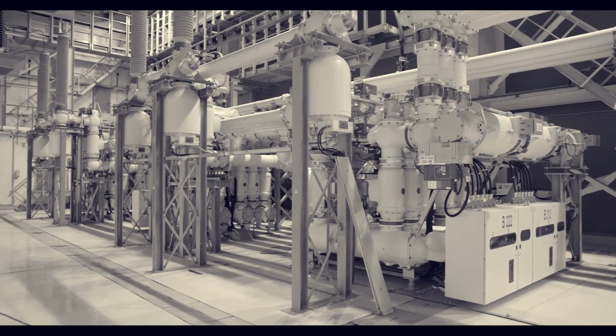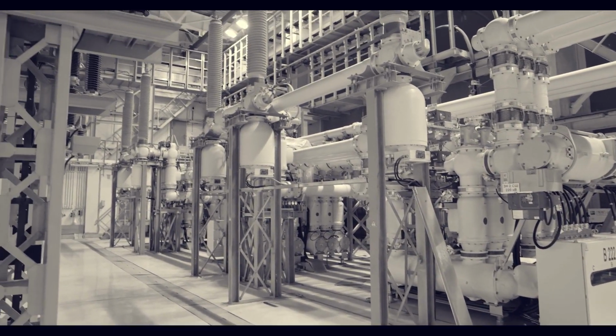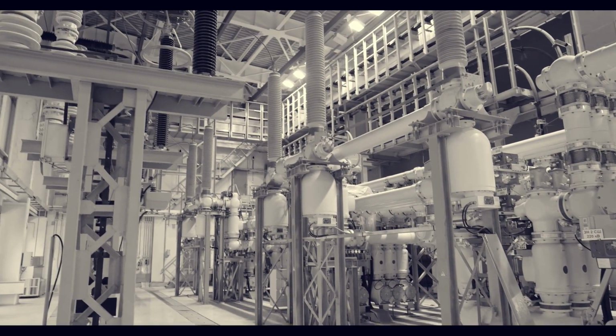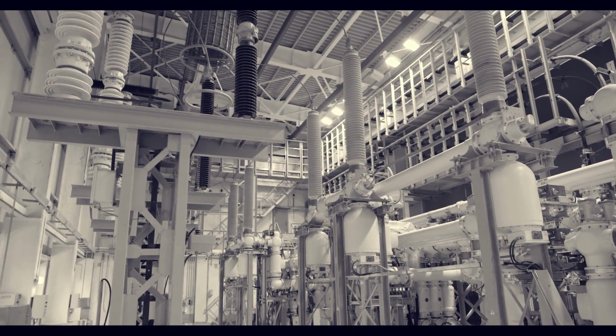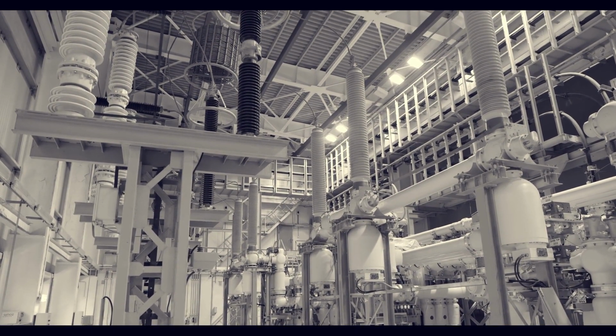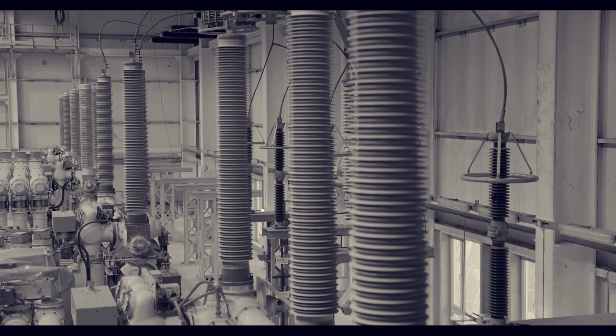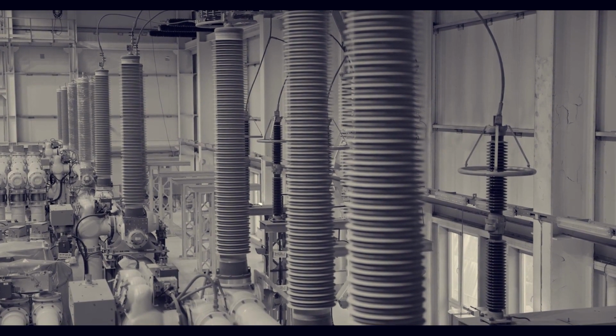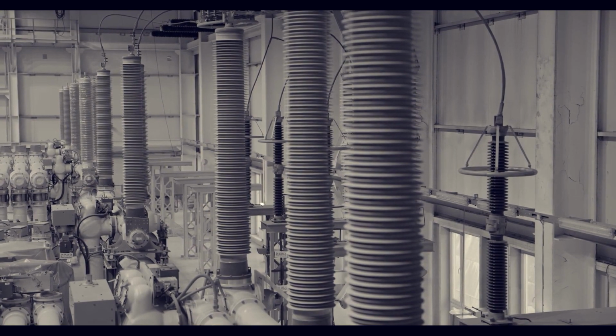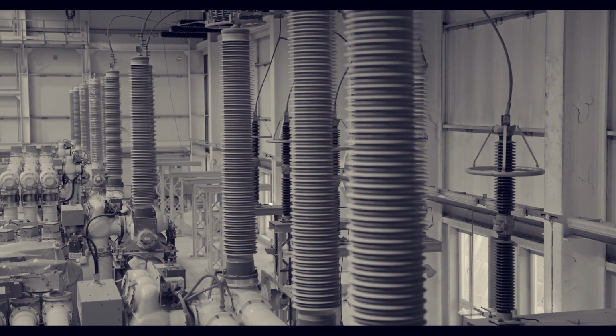A 500 megawatt gas turbine generator weighs hundreds of tons. It spins at exactly 3,600 rotations per minute, 60 rotations per second, locked to the 60 Hz frequency of the US grid. That spinning mass stores an enormous amount of kinetic energy, not in a battery, not in a capacitor, just in the rotation. Engineers call this inertia.